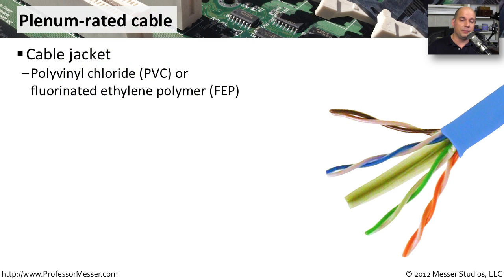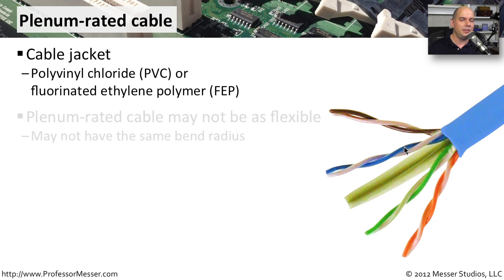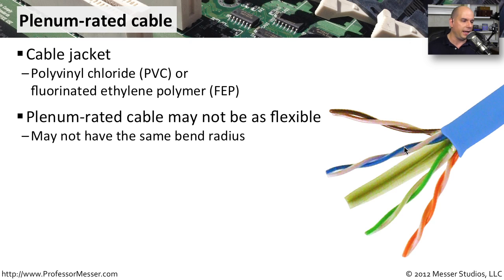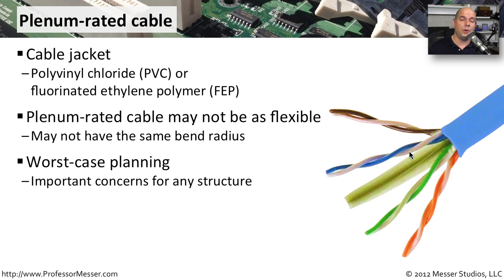The most important part of a plenum-rated cable is the cable jacket around the twisted pairs. This jacket may be PVC (polyvinyl chloride) or FEP (fluorinated ethylene polymer). This also causes the cable to be less flexible — it has a different bend radius and is not used for everyday cabling. The reason we use plenum cable is to limit what would happen if a fire occurred. A normal cable is much more flammable, and the plenum's fresh air supply could allow fire to move across a floor. Using plenum-rated cable minimizes that impact and limits the movement of fire.